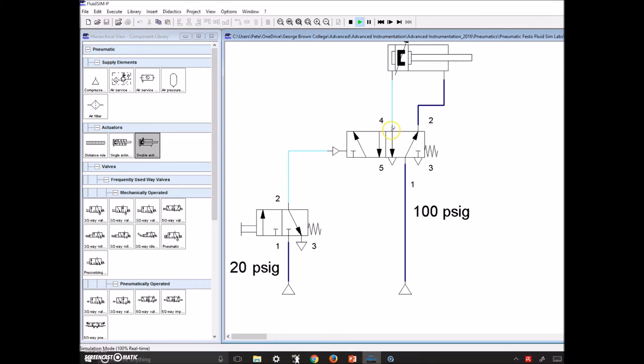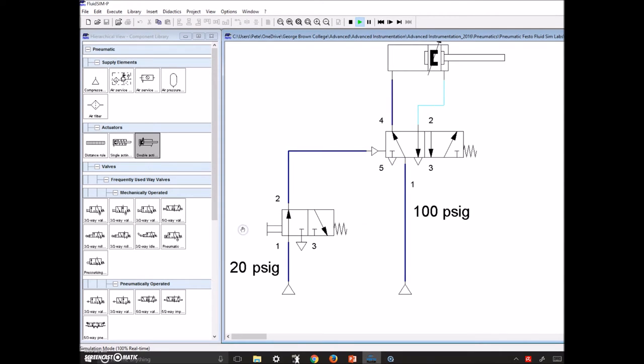The additional ports are port four and port five. In this rest state, air is traveling from number one up to port number two, pushing back on the double acting cylinder. Any air in here has a path to go from four to five and exhaust to atmosphere. When I press this push button, that toggles the air — you can see it going to the initiating port, toggling us over to the other position of the 5/2. The double acting cylinder extends because air travels from number one over to number four, and air trapped inside exhausts from two out to three.